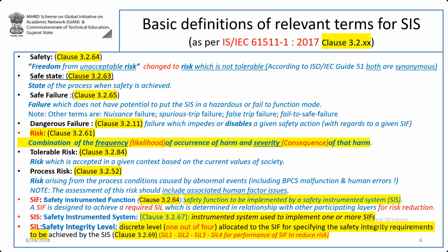Now, third is safe failure, which is a failure that does not have the potential to put the SIS in a hazardous or fail-to-function mode. The note written in the standard describes it as a nuisance failure. Sometimes the plant trips, sometimes your laptop goes blank, and you don't know why. When you don't know why it failed, maybe it is a safe failure. You may be able to restart it again, but you do not know. It is a safe but undetected failure. The failure is detected because it has failed, but why it has failed is not detected. So it is a safe but undetected failure. A safe failure may be detected or undetected.